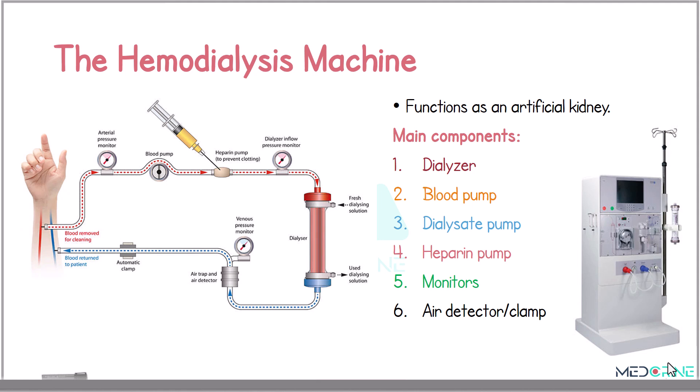A hemodialysis machine functions as an artificial kidney. Some of the main components of this hemodialysis machine include a dialyzer, a blood pump, a dialysate pump, heparin pump, monitors, and air detectors. You can have a look at this image to locate each of these components.